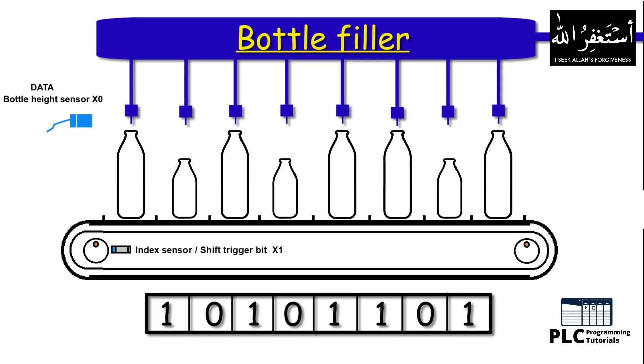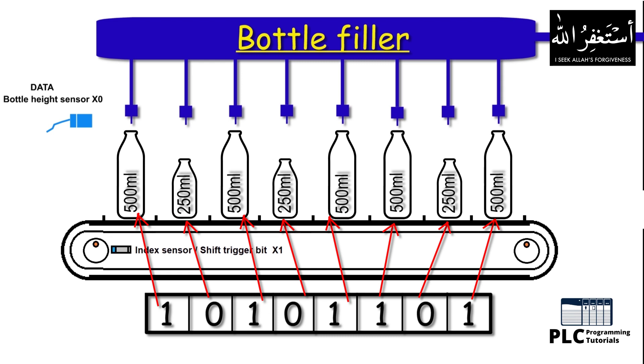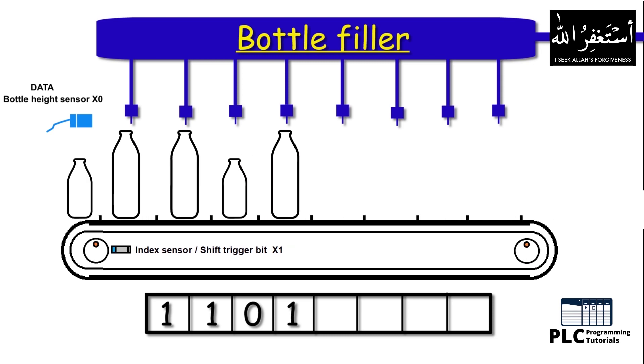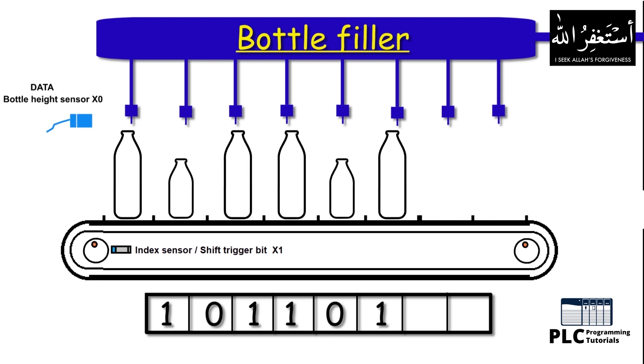In the end, we have eight bottles of mixed size in the filler, and we can track the location and size of the bottles under each filling nozzle using the data bits stored inside the shift register — zero for 250 ml and one for 500 ml. We can use these data bits to control the filling time of each nozzle, controlling how much volume we need to fill in each bottle. This way we can fill 500 ml in the big bottle and 250 ml in the small bottle. This is a basic example to show how a shift register works and how we can use it to make programming easier.